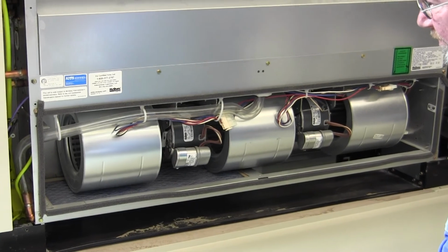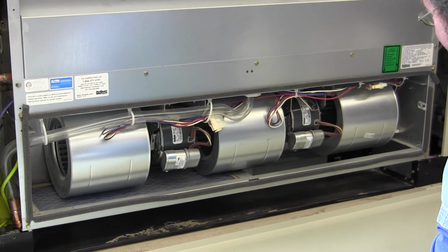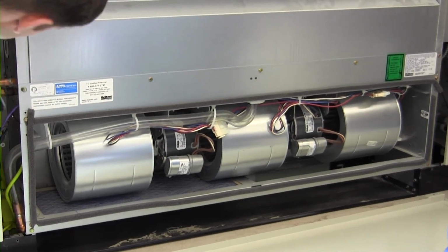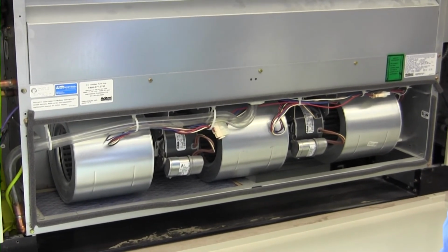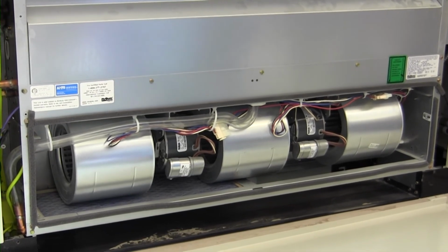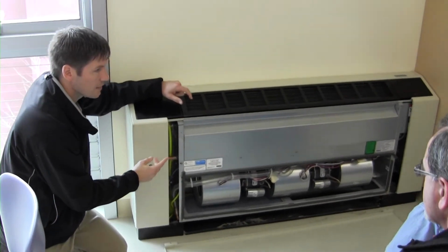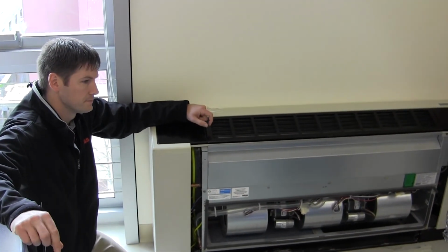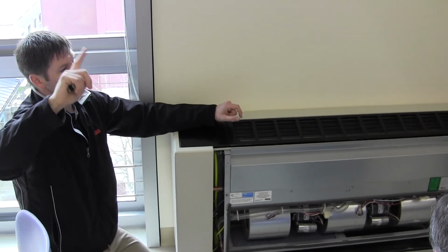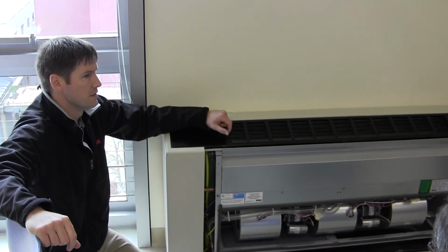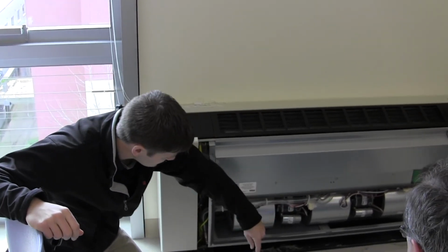It changes over like the ceiling. Radiant panels? Is there a water pipe over there too? No, there's only 2 pipes over here. But yeah, it changes over with the ceiling. So it's a 2-pipe heat and cool unit. These 2 pipes going in can either heat with hot water or cool with cold water, so there's some changeover somewhere for heating and cooling. Throughout the building, you'll see these perf panel ceilings. Those are radiant heating and cooling panels, and the room itself switches over from heating water or cooling water. That makes sense why the condensate trap is here.